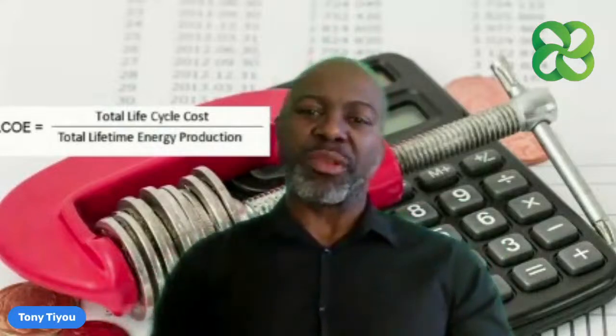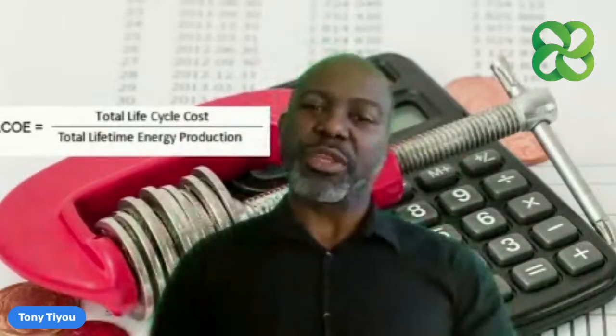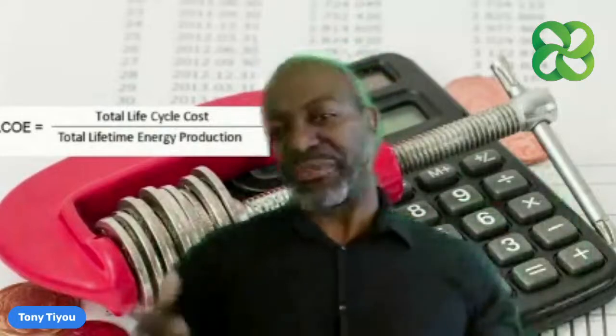So just to give you an idea of what the LCOE could be for the 1 megawatt solar plant we looked at since the start of this project. It would depend on many factors: location, technology, price specifics, and so on and so forth. But to give you an idea, you can look at anything between 5 cents to 15 cents per kilowatt hour. That's what you're looking at for a solar PV plant. It gives you an idea, but like I say, it varies on many things. But at least you get an understanding. That's what the LCOE is. It's a very, very important measure. And if you're an investor, I'm sure you keep on tracking that on a daily basis.